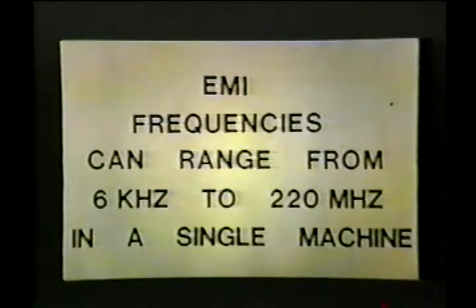EMI is common to all machines. It can cover an extremely broad spectrum of frequencies. In a particular hydroelectric machine, this was from 6 kilohertz to 220 megahertz. Similar machines, that is those with similar stator designs, produce a similar spectra of EMI. One of the nice features about this type of testing is that early incipient fault detection is possible. EMI does tend to increase as deterioration increases, and likewise EMI is stable if the defect is stable. And most importantly, certain types of EMI are produced by defects only at certain frequencies.